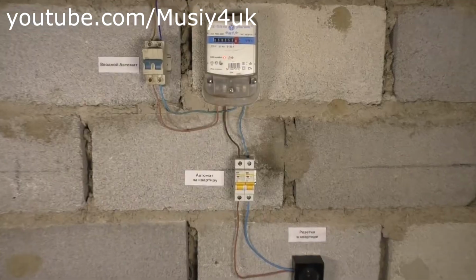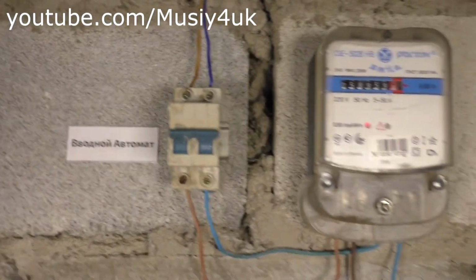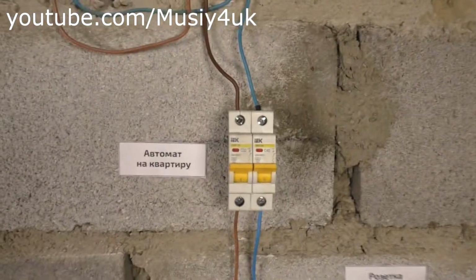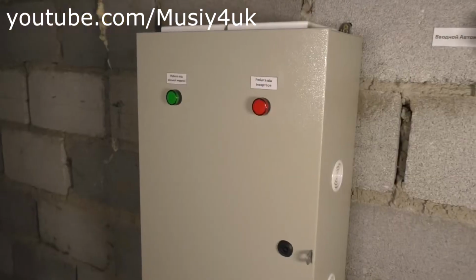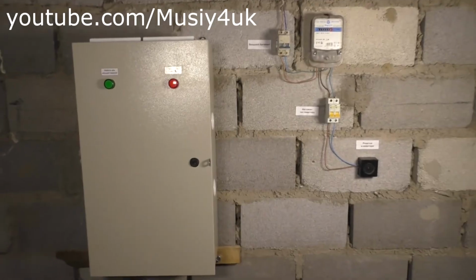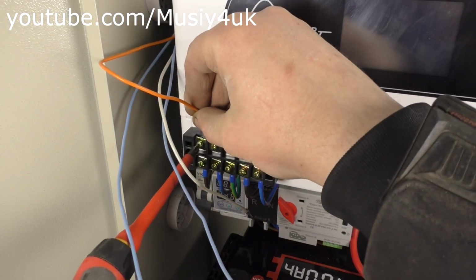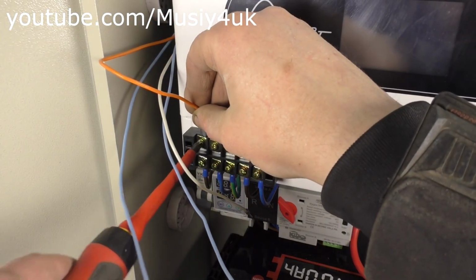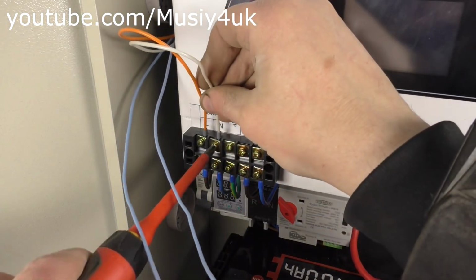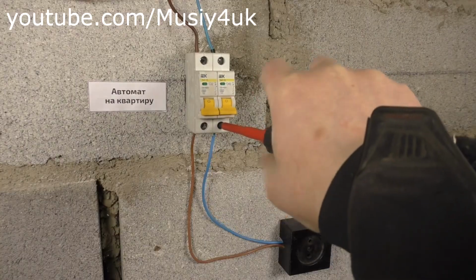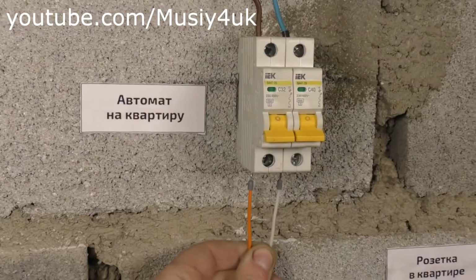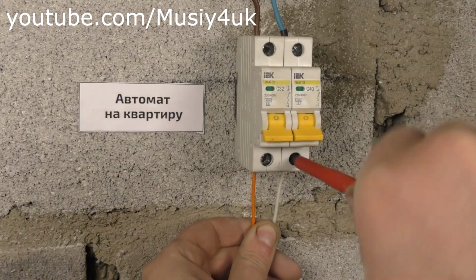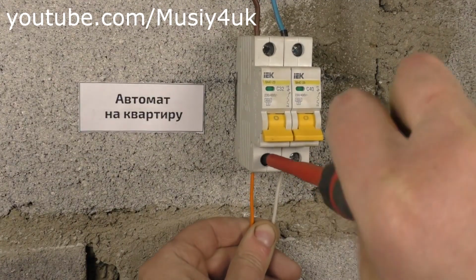Now I'll show you how to connect this system to your apartment. Here's a standard diagram with a main circuit breaker and one for the apartment. You need to install the backup power system nearby and run a 5-conductor or 4-conductor cable into it. Connect 2 wires to the terminals labeled input. Then, from the circuit breaker that goes to the apartment, you need to disconnect the apartment wiring. Instead of it, connect the same wires that we connected to the terminal block labeled input.